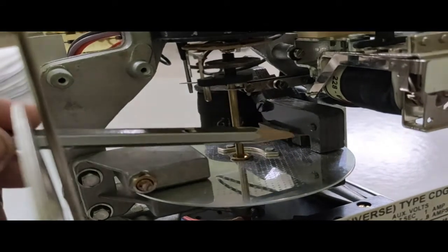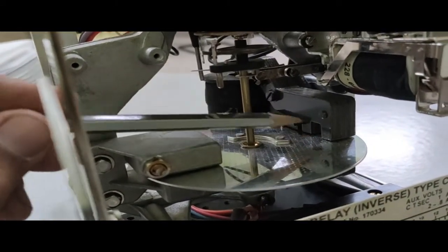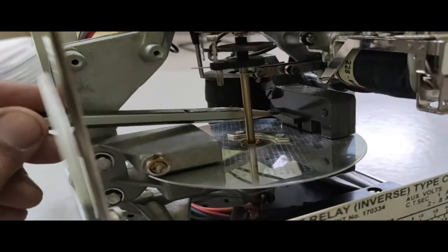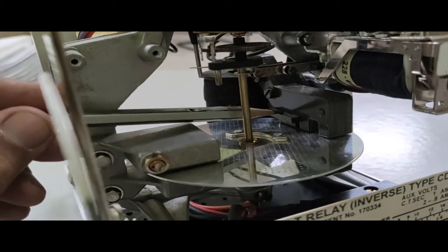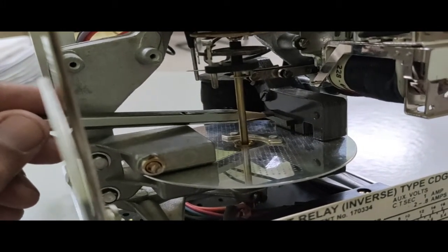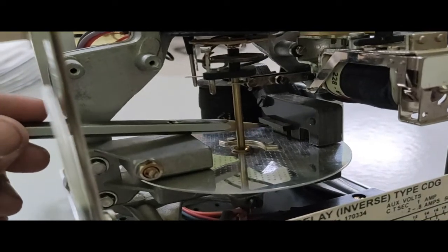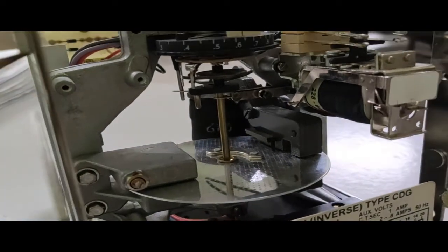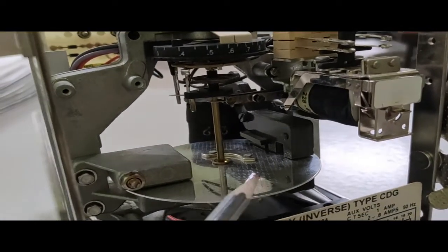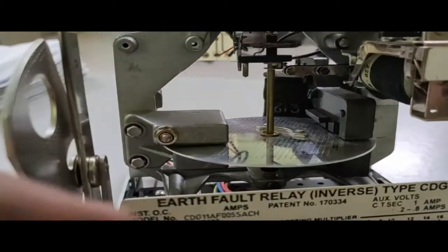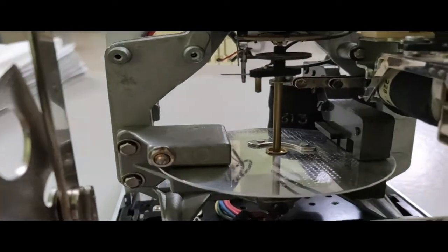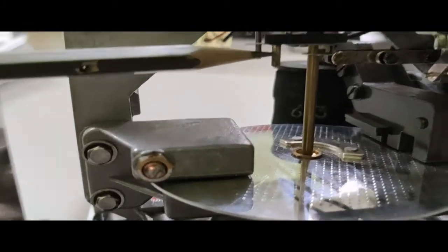So that means the flux generated by the unshaded pole and the shaded pole have a phase difference, due to the shaded ring connected here. Due to the interaction of these two fluxes, some force exists on the aluminum disc, and the disc starts rotating, and as the disc starts rotating, it contains two things. One is this one.